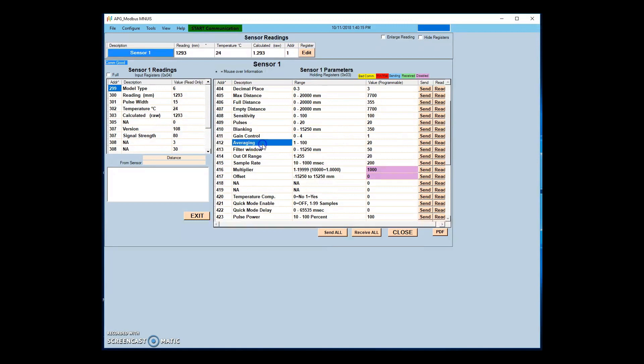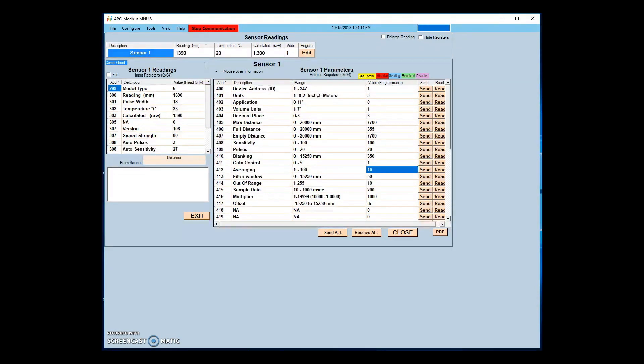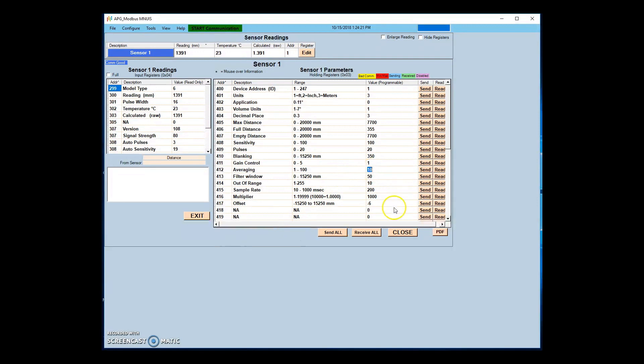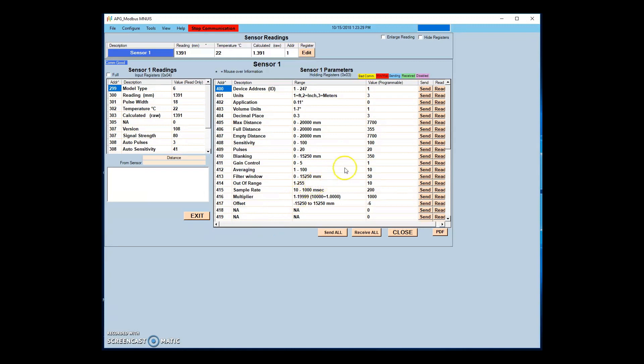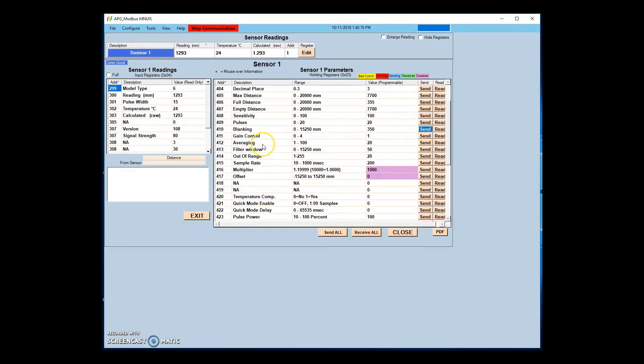Averaging filter window, out of range, and sample rate parameters work together to stabilize the readings from the sensor. Averaging sets the number of received signals to calculate for the displayed reading. The filter window determines the difference allowed between the current reading and received signals for a signal to be qualified and accepted into the averaging buffer.